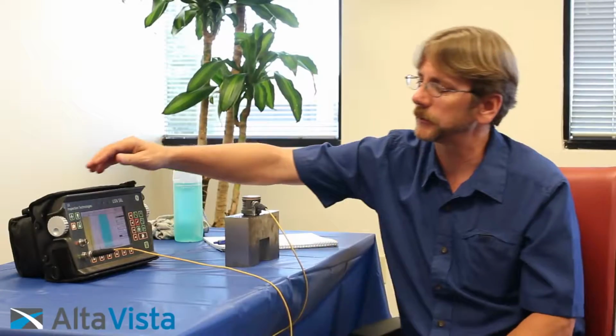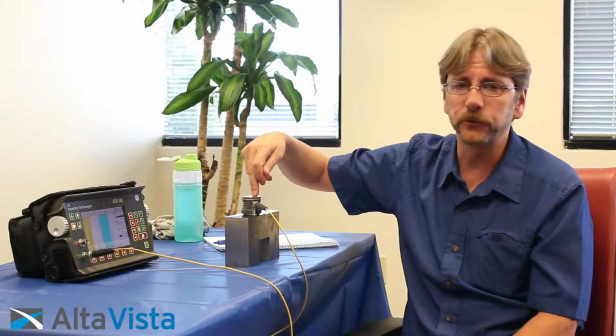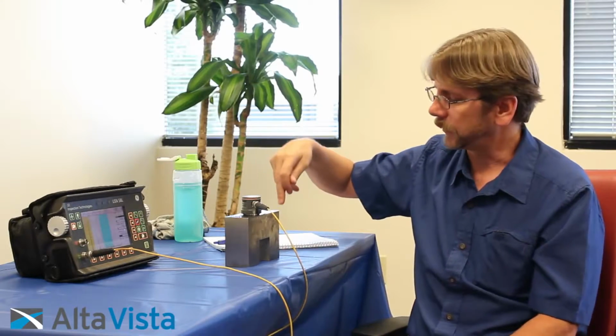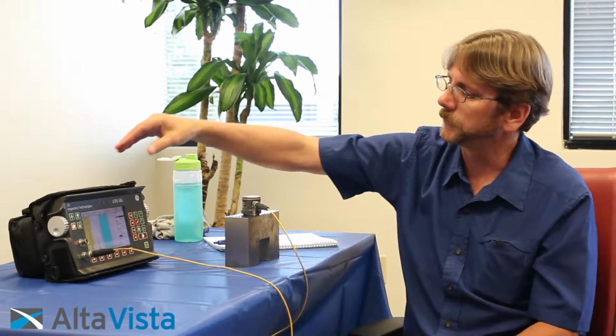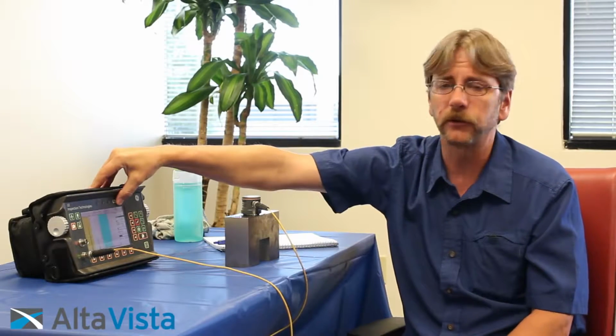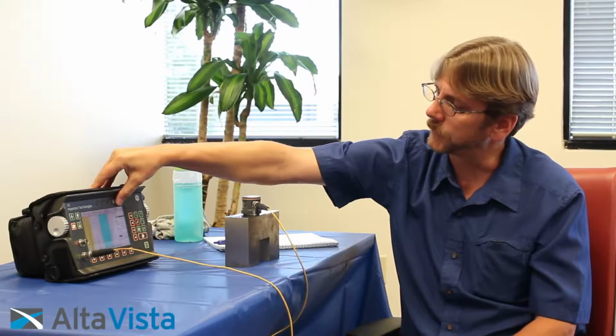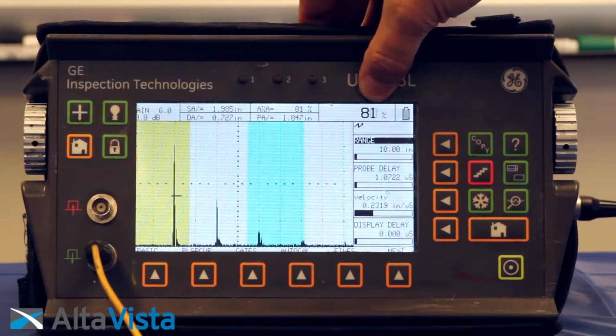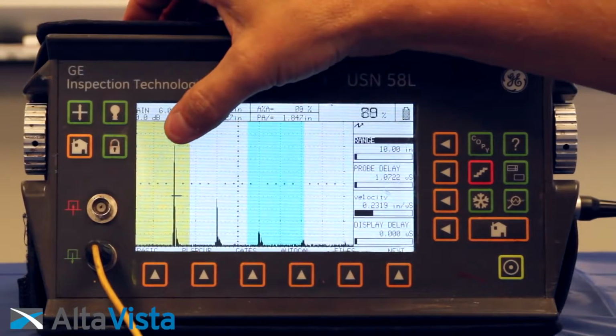So here we have an ultrasonic unit. We have a transducer that's 2¼ megahertz, and we also have a DS block. So what we're going to do is look at the percentage of screen height of the signal. Right underneath my thumb, it indicates it's 80% full screen height, which is where this indication is.